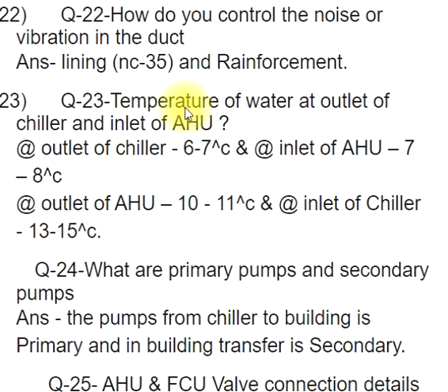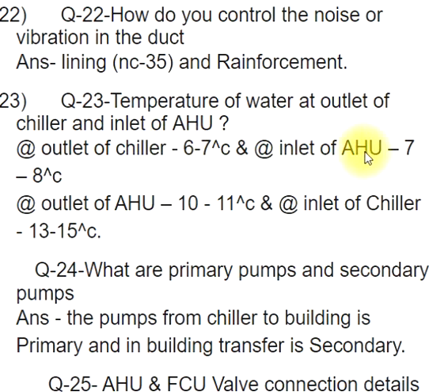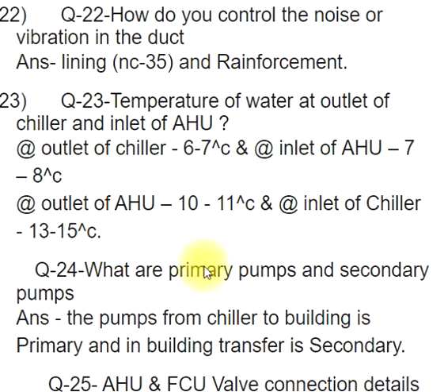Q23: Temperature of water at outlet of chiller and inlet of AHU. At outlet of chiller: 6–7°C; at inlet of AHU: 7–8°C. At outlet of AHU: 10–11°C; at inlet of chiller: 13–15°C.